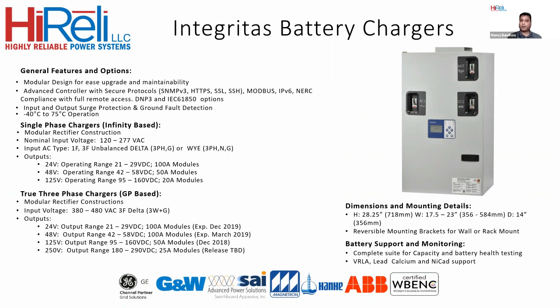This is a modular design, giving you the ability to have multiple independent voltage outputs. For example, you can have a combination of a 48 volt output and a 125 volt output. The picture shows the two different versions, with physical dimensions of 24 inches wide, 26 inches deep, and about 84 inches high, so much taller than the wall-mounted units.